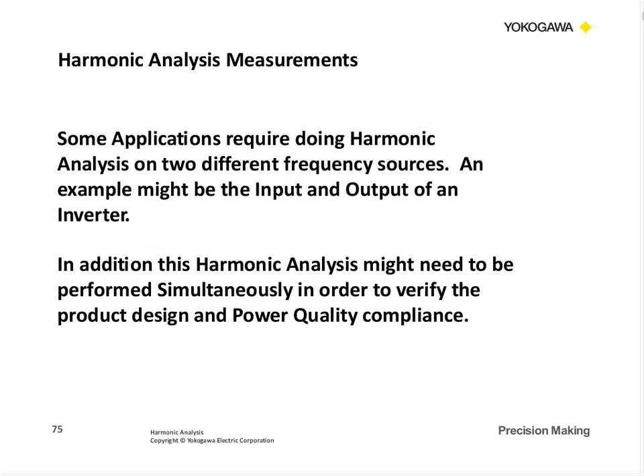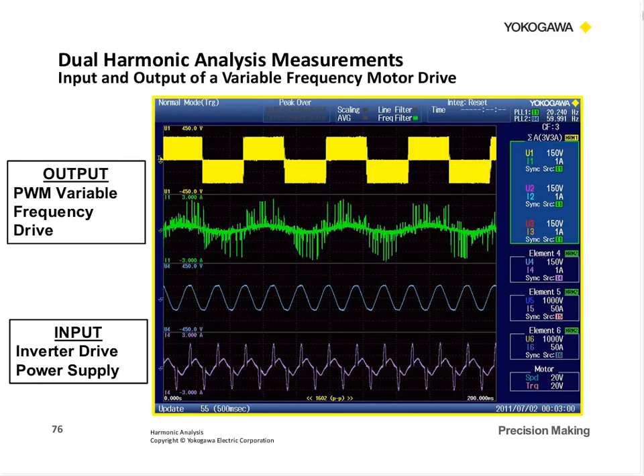Sometimes some of our applications require doing harmonic analysis on two different frequency sources, such as an input and an output. With our newer instruments, we can perform the harmonic analysis simultaneously with the standard power measurements. So here's a dual harmonic application. As an example, we could look at the output of a drive and look at the input to the inverter drive or power supply.